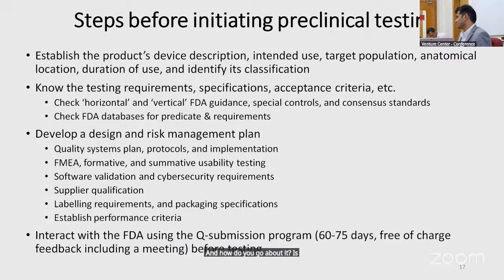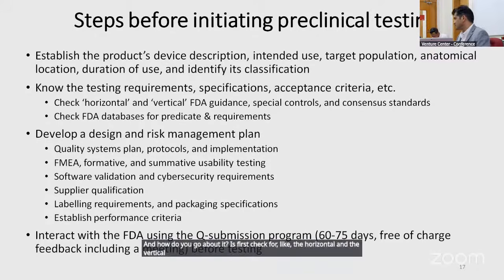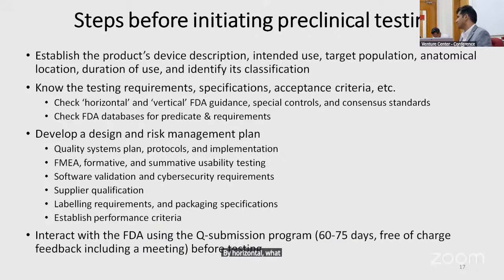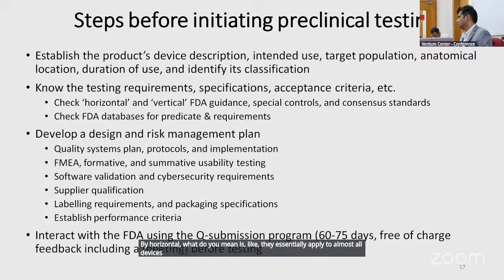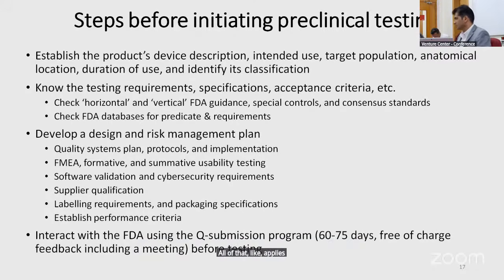First, check for the horizontal and the vertical FDA guidances. By horizontal, what I mean is they essentially apply to almost all devices, like biocompatibility, electrical safety, electromagnetic compatibility, right? All of that applies generally. But vertical guidance is specific to a device. So an orthopedic implant or maybe a polypropylene mesh, they have their own guidance document. So you need to know both the general guidance documents for each category of testing, as well as the ones specific to your own device, and also the special controls and consensus standards that might be there.